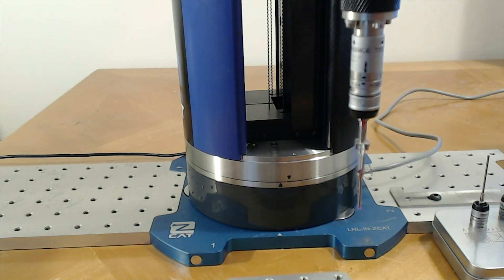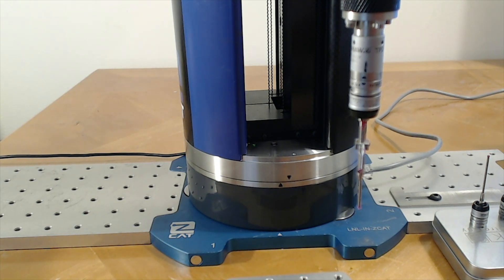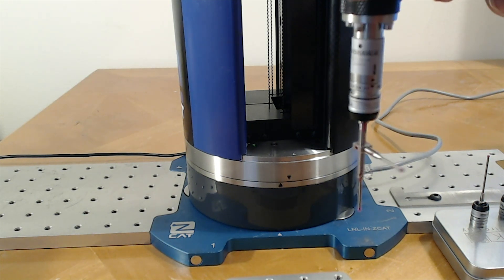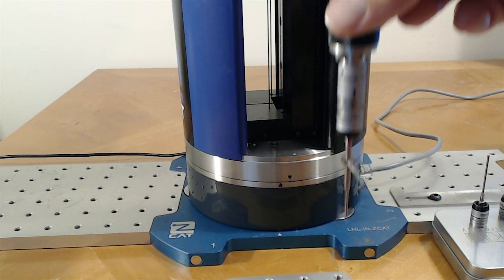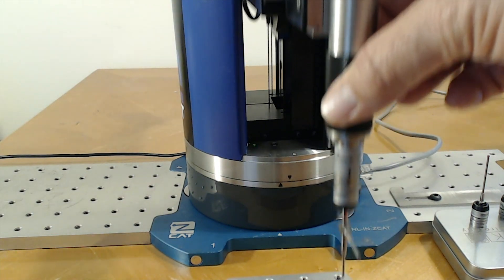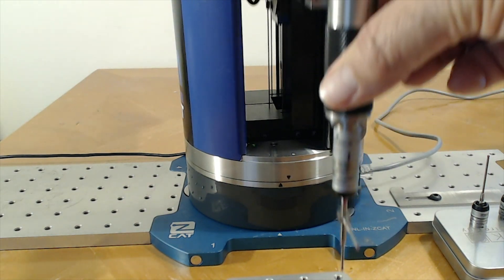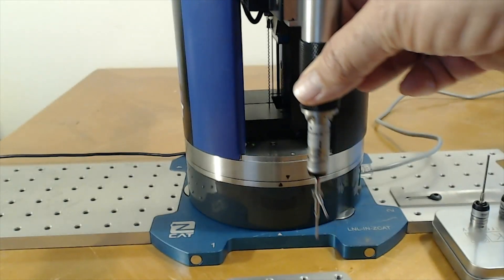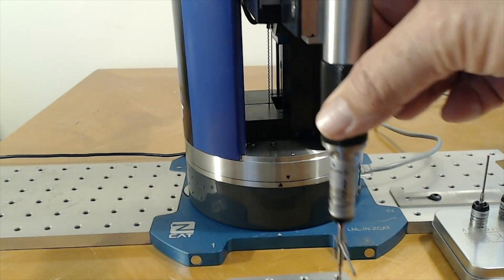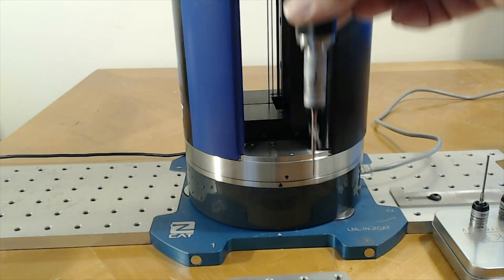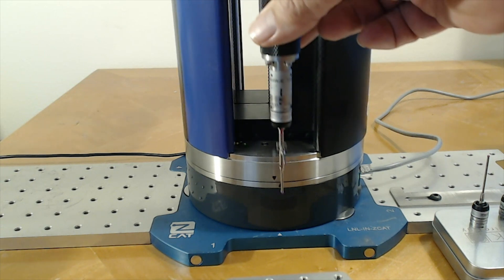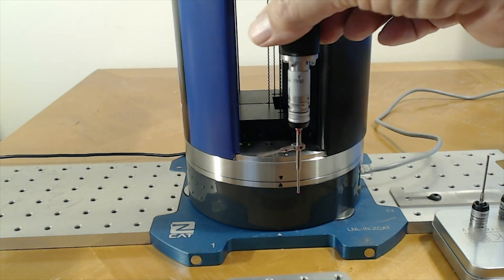We don't need that star configuration that the typical TP20 would have because the horizontal probe can rotate. We have a linear scale in the Z axis, a linear scale in the cross axis, so there's four axes of measuring in the ZCAT.